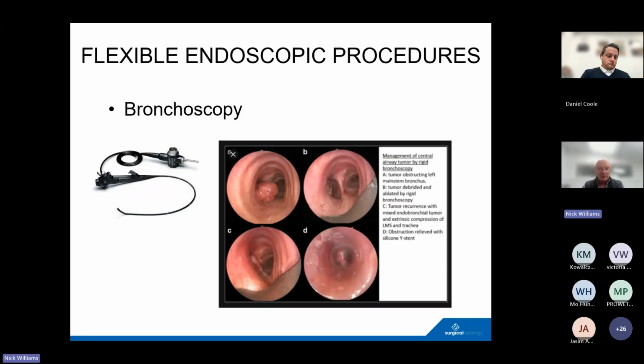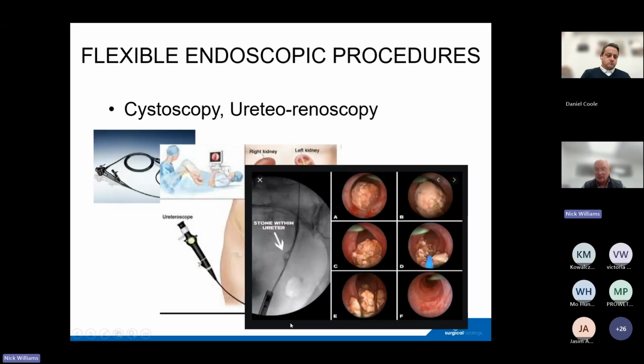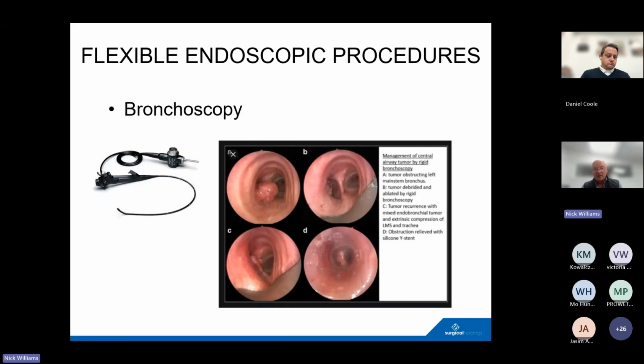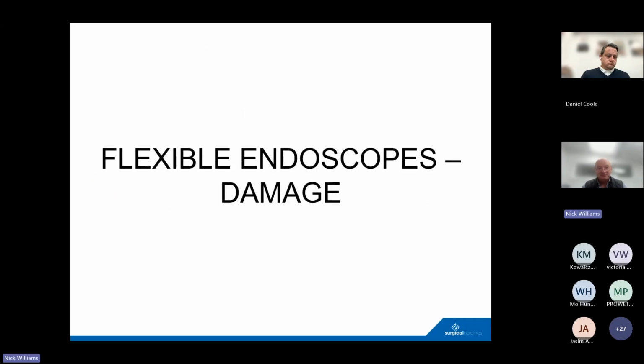And as more things go through the scope, particularly, for example, a laser, like I showed you here, if you're lasering, you've got a laser fiber which can be quite sharp. So if you've got a tip that's bent quite a lot, that laser fiber can damage the internal channel of the scope. And as therapeutics has taken off, damage internally has also taken off. So let's talk about damage.